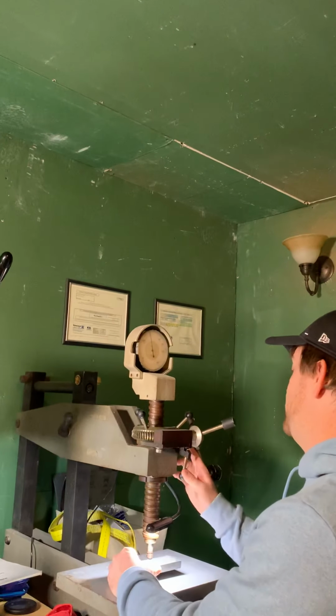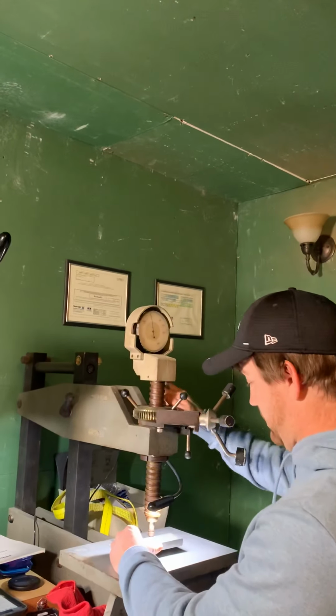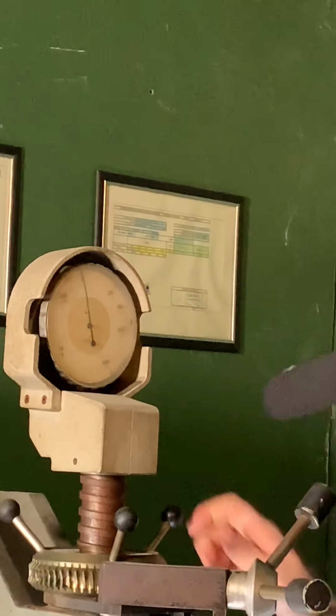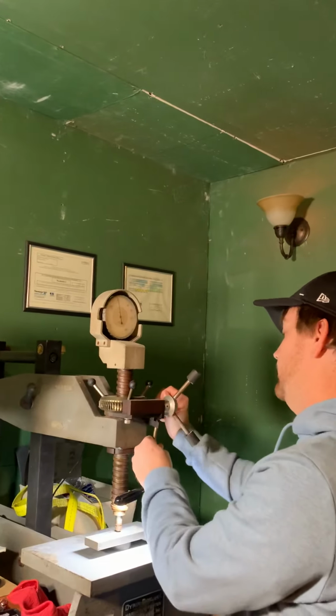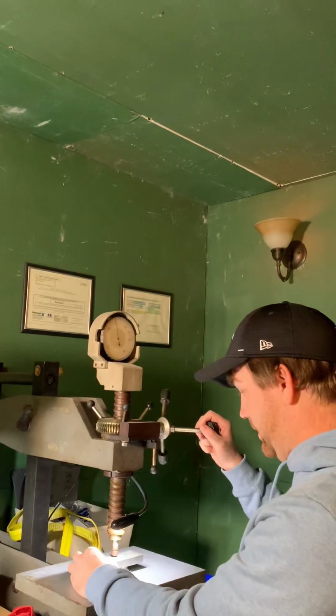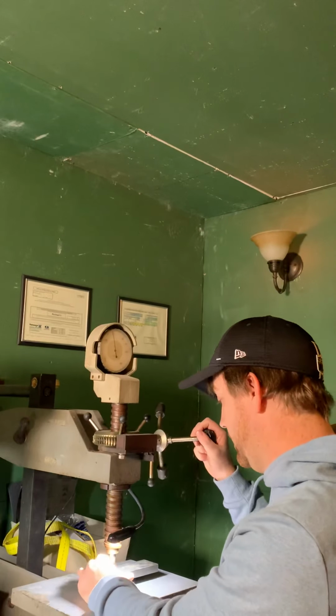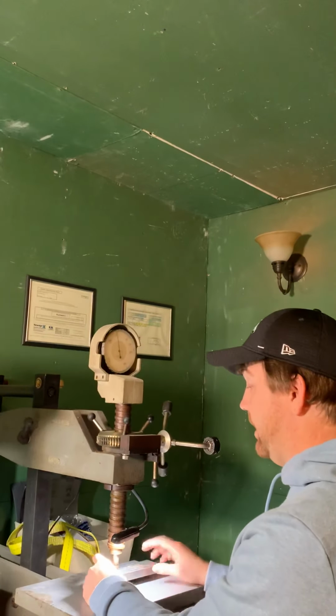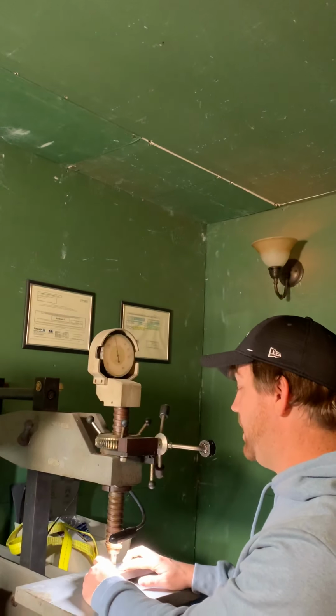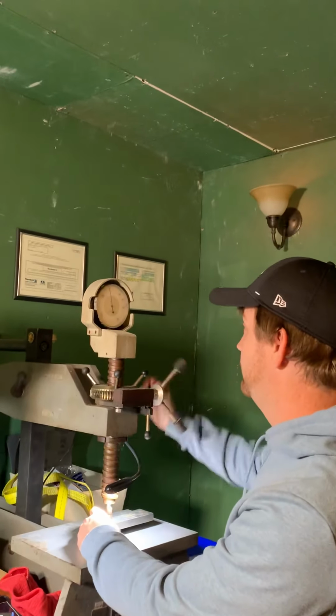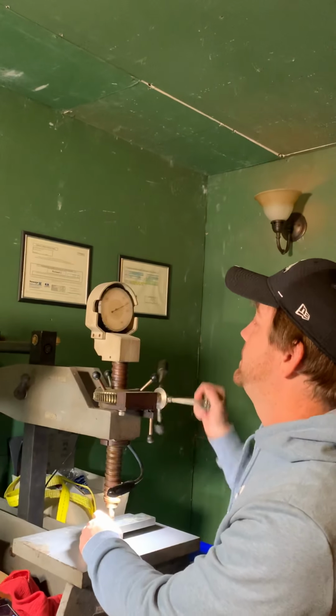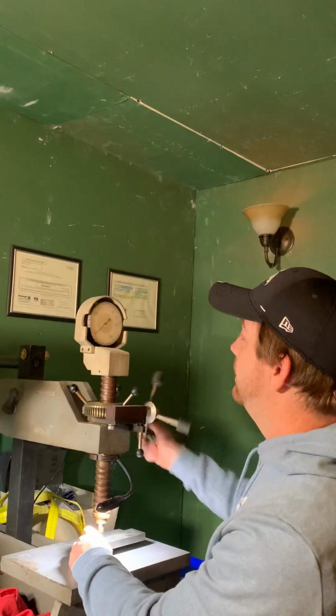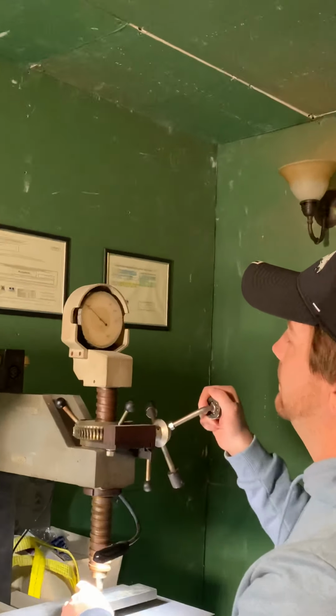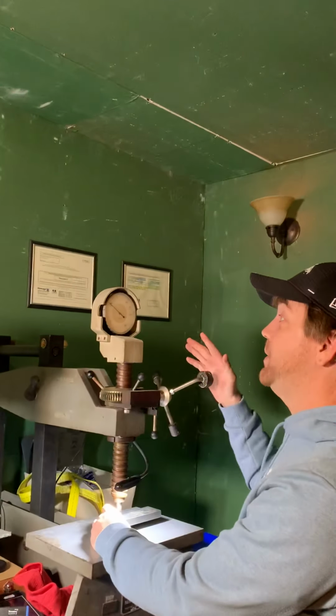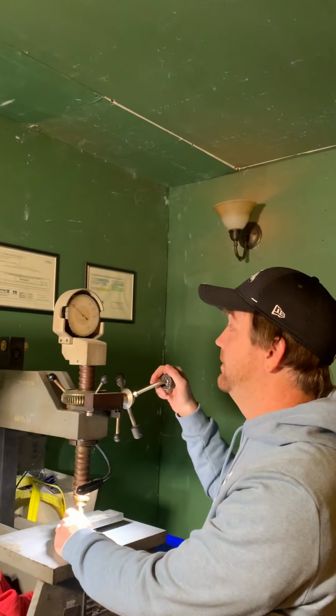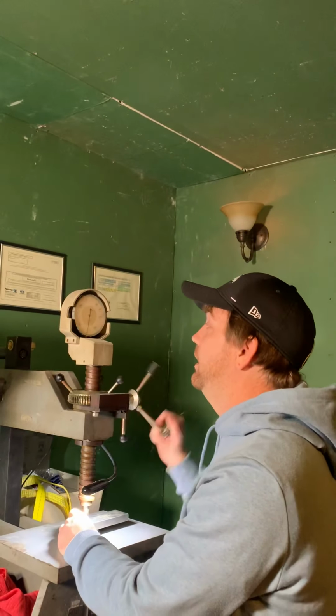So to take my initial as found tests, what I would do is I would find a spot that it's at least 3 indentations away from any other spot on the block. Begin to apply the force up to 3,000 kilograms. Allow 3,000 kilograms to be applied for 10 seconds. And then release the load.